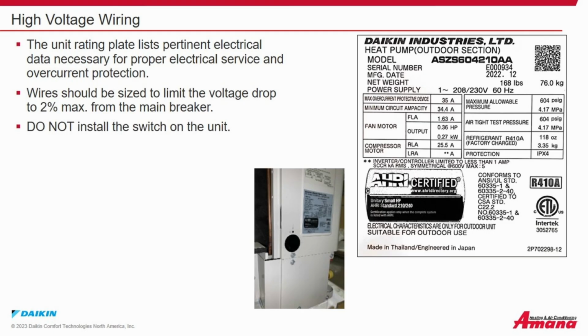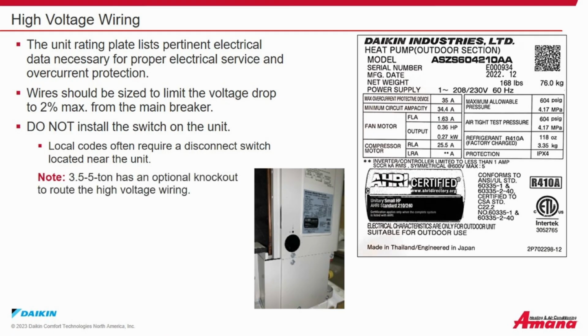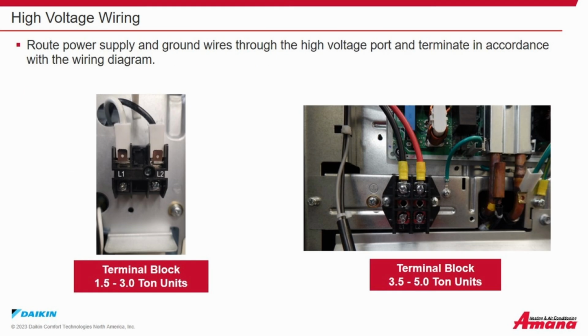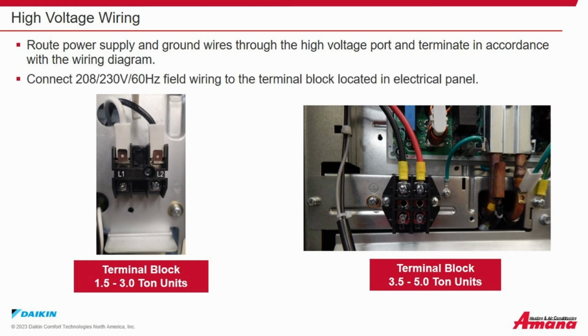Do not install the switch on the unit. Local codes often require a disconnect switch located near the unit. Note, the 3.5 to 5 ton has an optional knockout to route the high voltage wiring. Route the power supply and ground wires through the high voltage port and terminate in accordance with the wiring diagram. Connect 208, 230 volt single phase field wiring to the terminal block located in the electrical panel. Below you will see the terminal block for the 1.5 to 3 ton and for the 3.5 to 5 ton units.